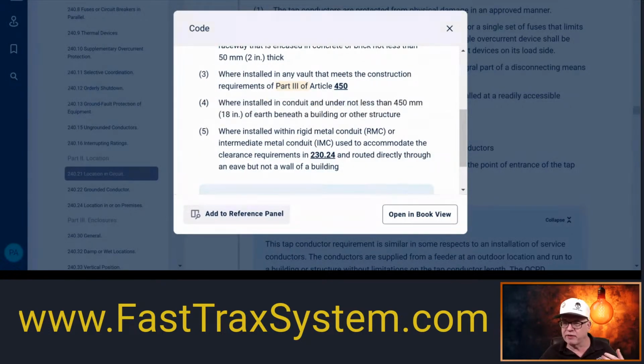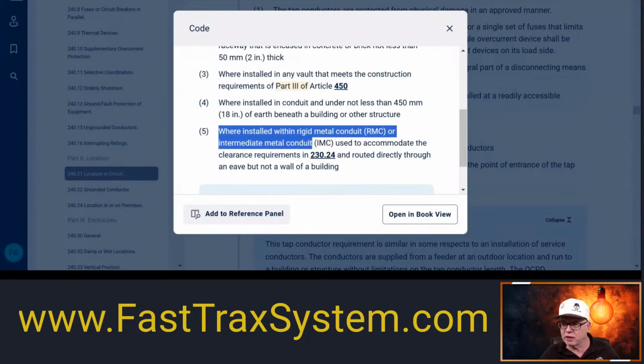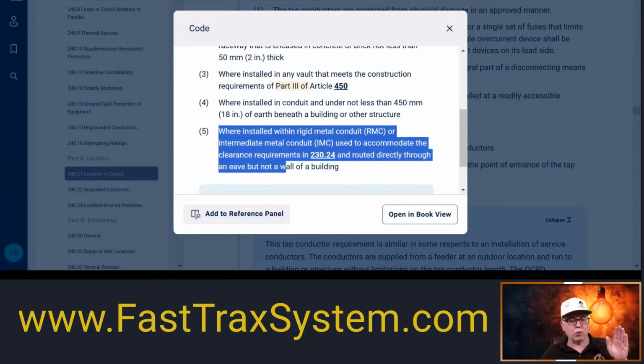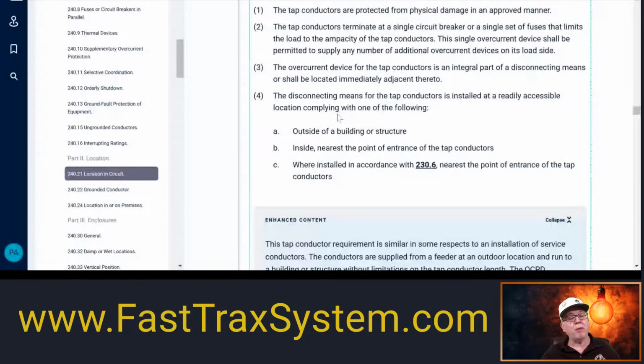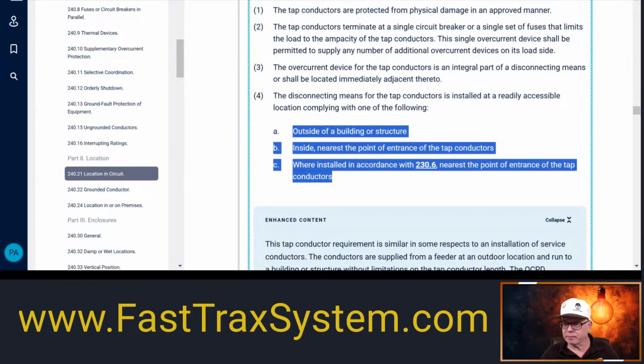Or installed in rigid metal conduit or intermediate metal conduit used to accommodate the clearance requirements of 230.24 and routed directly through the eave. Totally different rule than just running it into the building and encasing it in concrete to, say, get to a second floor where this is going to terminate. You have all those options, but the moment it emerges out of that 2 inches of concrete, boom, it's got to hit that disconnecting means. So you have other options here to be able to do this, okay?